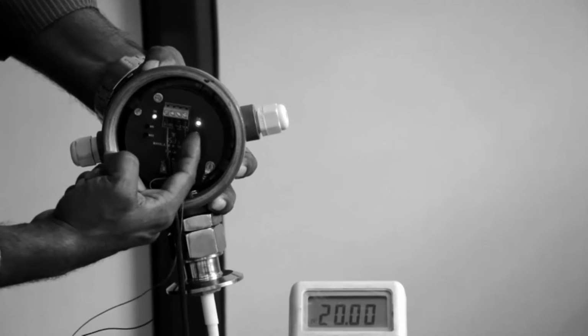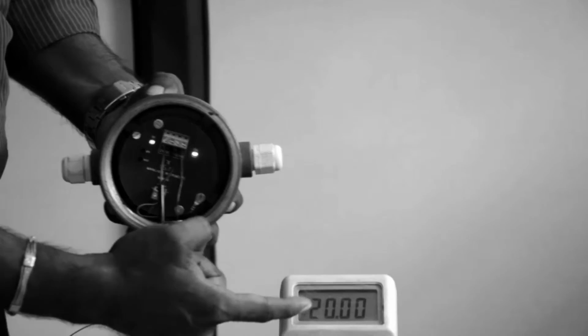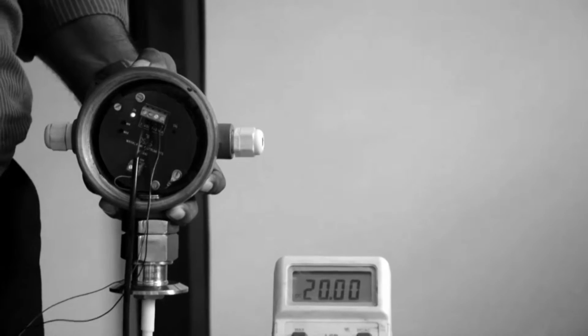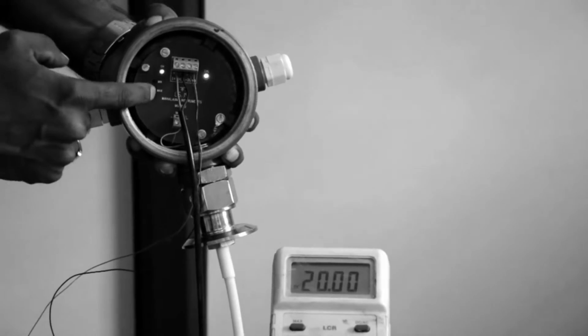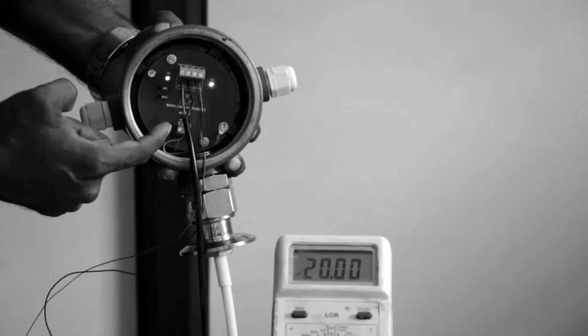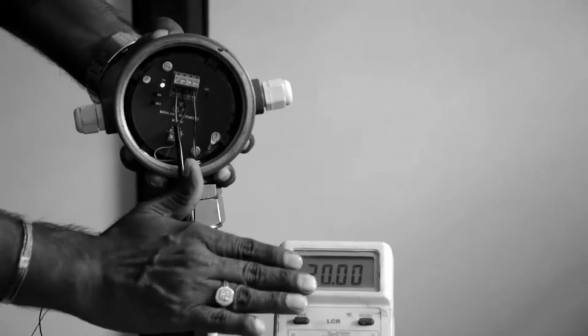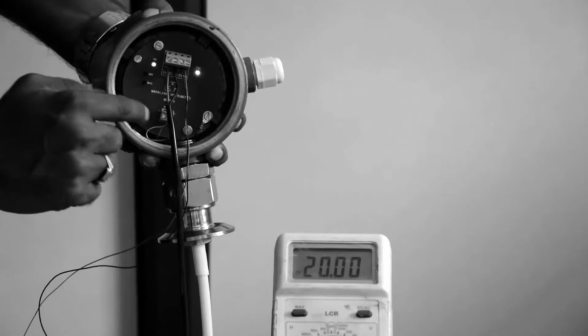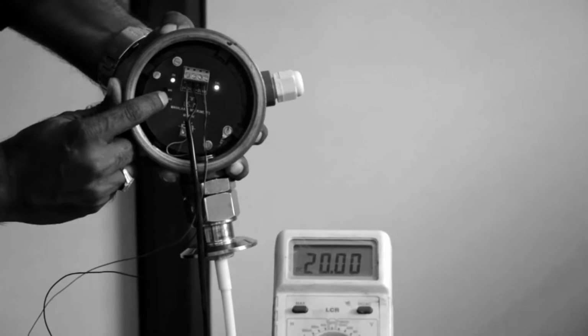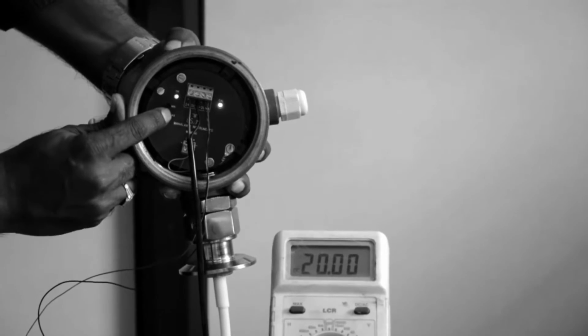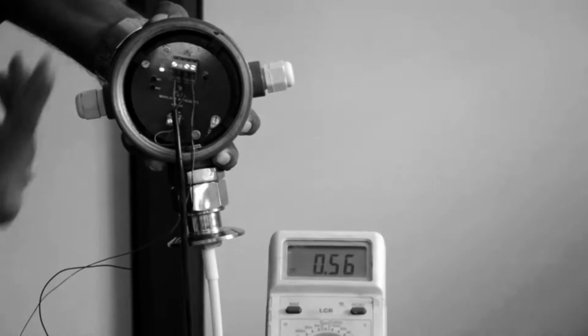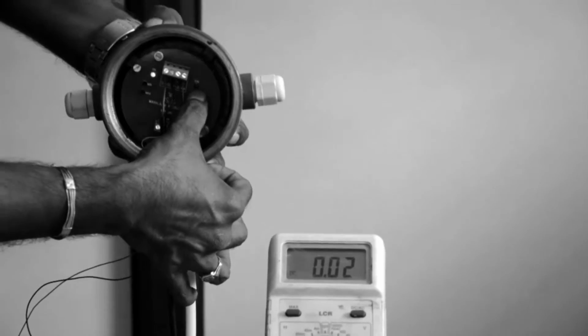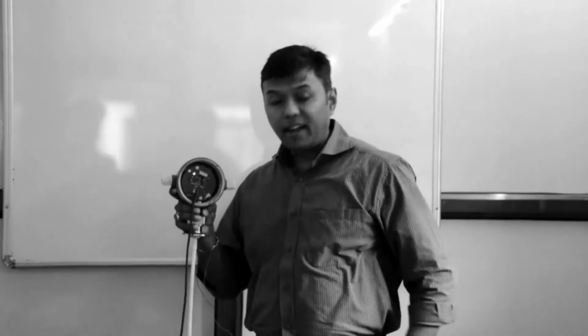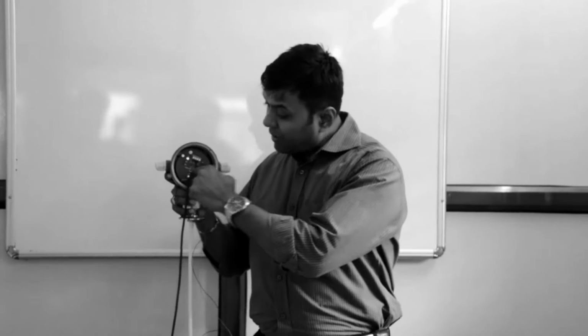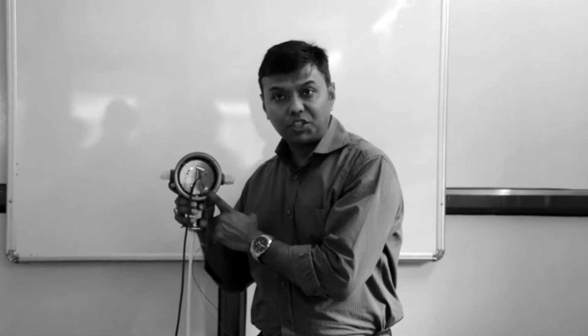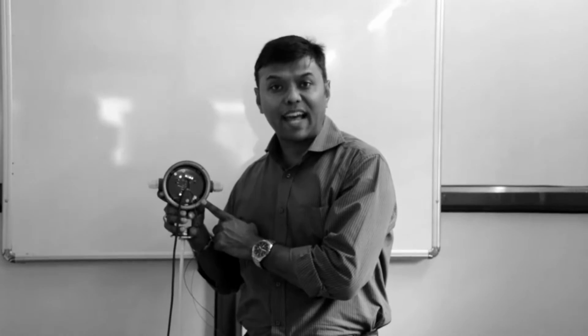Again you can see that the calibration LED has started blinking, and you can see that the multimeter is showing a perfect 20. Even in this case, if you want to increase or decrease the value, you can press the upper push button or the lower push button, and you can increase and decrease the value. Once your 20 milliamps is set, you can again press the maximum for 3 seconds, and you can come out of the calibration mode, and the calibration LED will stop to blink. And this shows that our electronic card is in perfect working condition. This is part 1 of the calibration process.